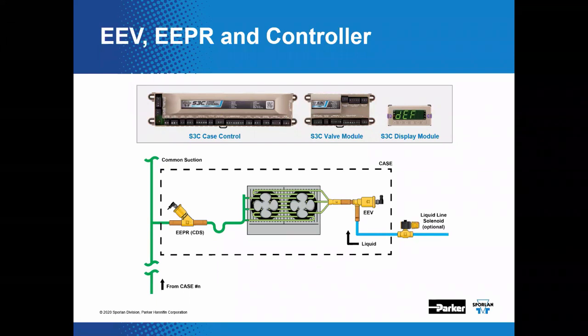In this example, 1 case controller and 1 valve module are required. The case controller will handle the normal case functions and receive the necessary sensor inputs for the EEV. The valve module here will drive the electric evaporator pressure regulator. The EEPR will regulate discharge air temperature, and the EEV will control superheat. The optional liquid line solenoid valve may be installed as a 1 per case or 1 per lineup.